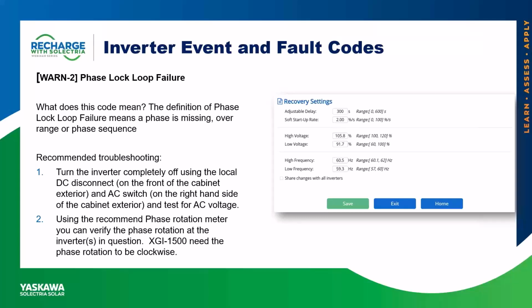The first code we're going to discuss here today is Warn 2, phase lock loop failure. Now, the word failure can come off as harsh and exaggerate the situation. When the inverter shows this code, essentially it believes that either a phase is missing, over range, or rotation is out of sequence. This code might come up during the commissioning process, especially if you don't have PTO.